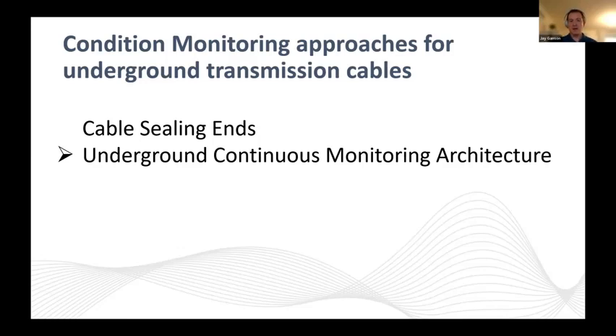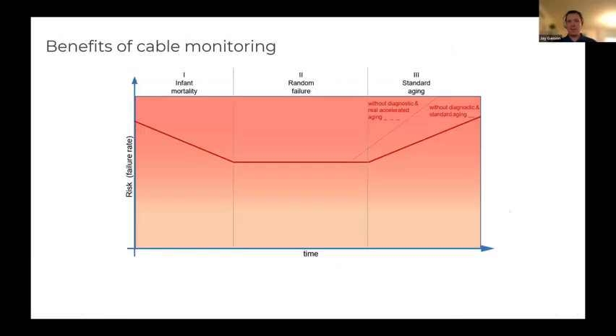But when we're talking about most buried cables that are going in today, and specifically types of cable not oil filled, like XLPE, partial discharge is really the primary way that we look for the insulation and the health index of that cable. We do that throughout the entirety of the life cycle of underground cables at Doble.